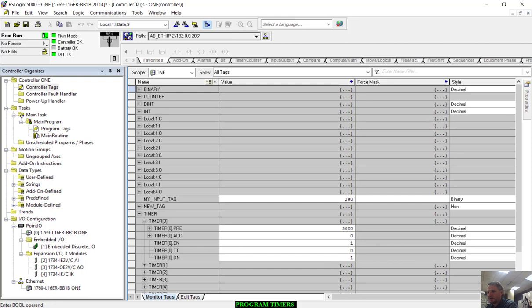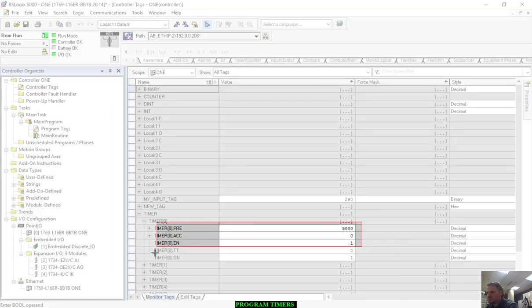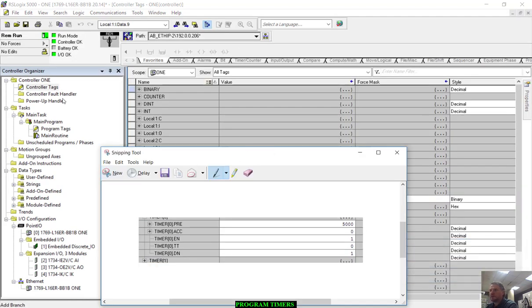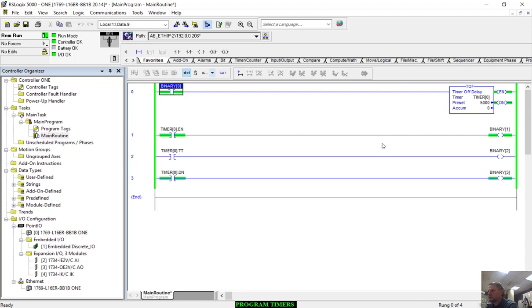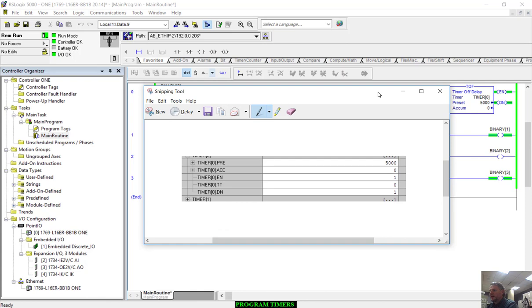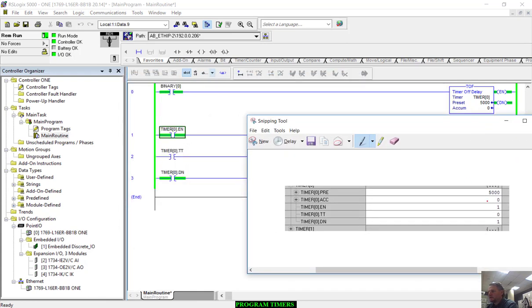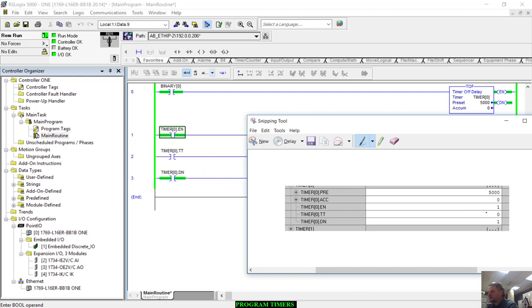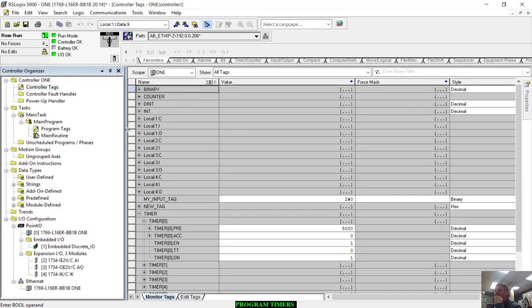If we look in the data table, we should see the same thing. Let's validate that. I have 5000 in the preset, zero in the accumulator, enable is on, timer timing is off, and done bit is on. Okay, so that all corresponds.